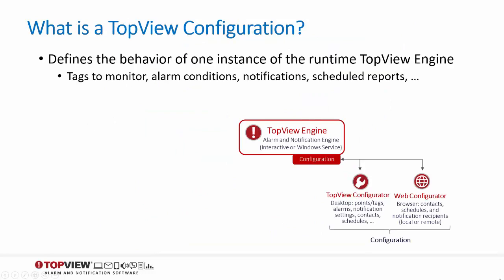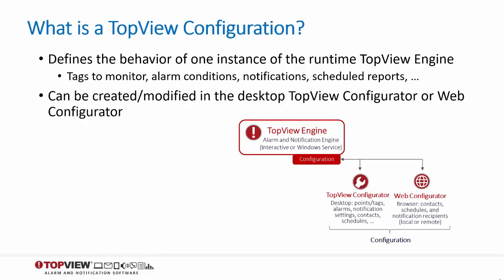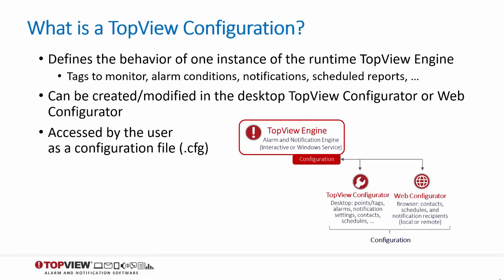Although many SCADA users will only run one instance of the Top View engine, we allow users to run multiple runtime engines. Each engine is a separate process. Larger installations may want to group their alarms into smaller sets, and therefore separate engine processes that run independently of one another. Each engine is controlled by a configuration that defines the alarms and notifications that the engine is responsible for. This configuration can be viewed and edited in both the desktop configurator and the web configurator. The user sees this configuration as a single file with a .cfg extension, although under the hood there are multiple files involved in the storage of the configuration settings.